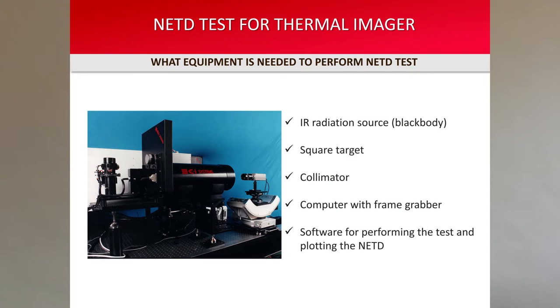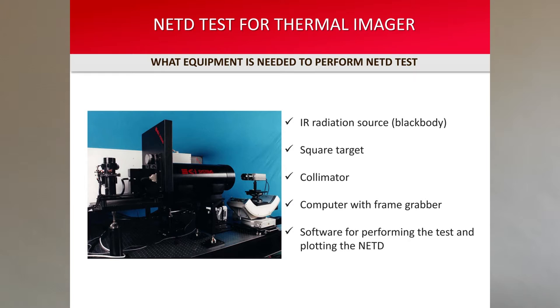To run the NETD test you need: first, an infrared radiation source, better known as a black body; second, a square target; third, a collimator; fourth, a computer with frame grabber; and fifth, software for performing the NETD test.